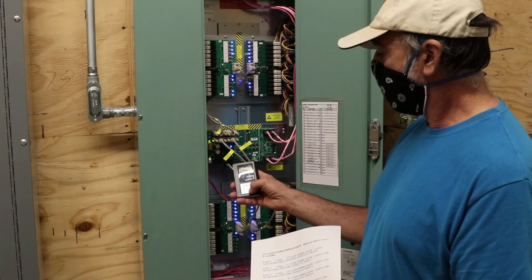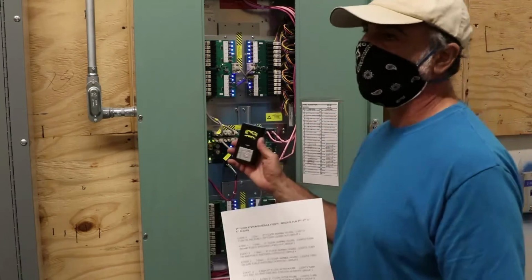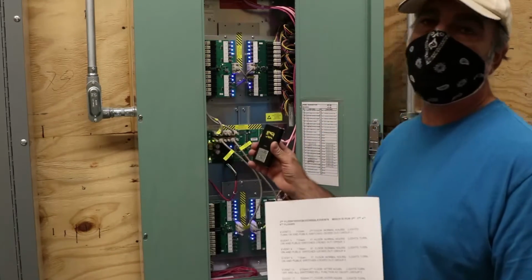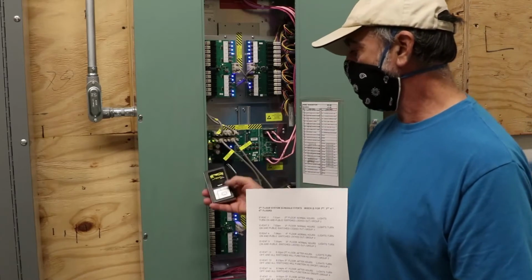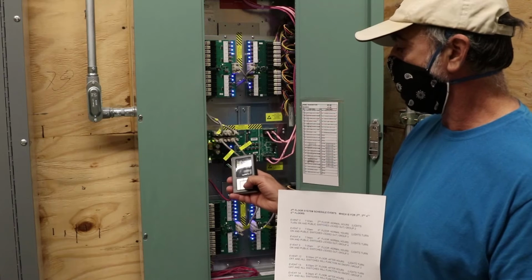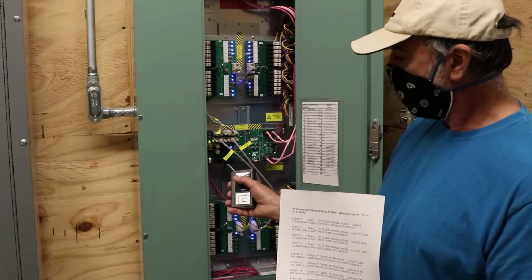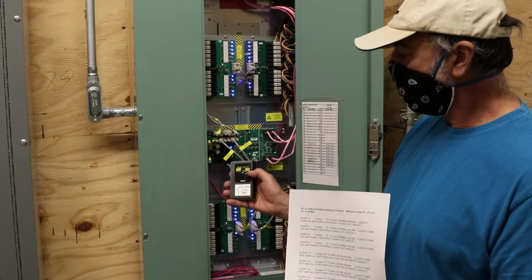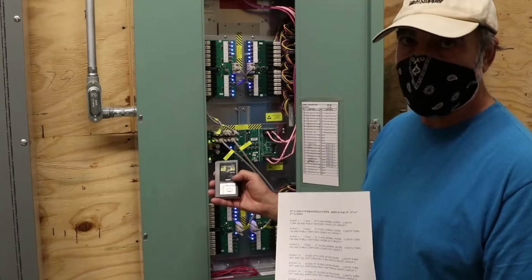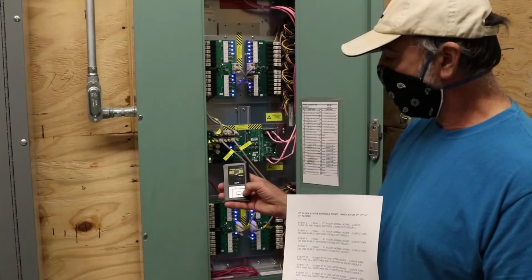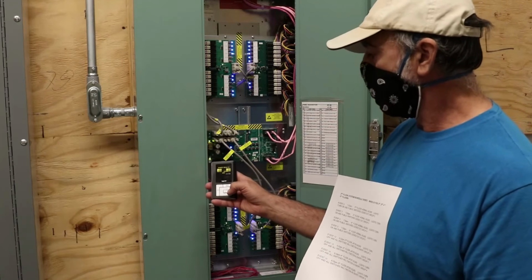One more thing down here, you could change the days. Maybe, let's use that 5th floor as an example. Maybe only on Thursday and Friday they don't have anybody there, so you could not have this happen on Thursday and Friday. So go to active days, and right now it lists all 7 days plus holidays, and they either have a Y or an N next to them, and you could change that. A Y means, yes, that day is going to work on that day.